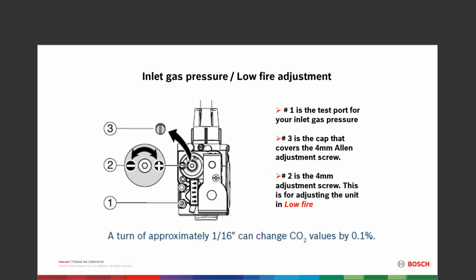So just 3 turns on the gas valve and then 1 turn on the gas throttle should get you going as a preliminary. The gas orifice itself should keep you from having to do that. So it makes life kind of easy. Once you've adjusted your low pressure and you're getting it close to where it belongs, then you're going to work on high pressure next.